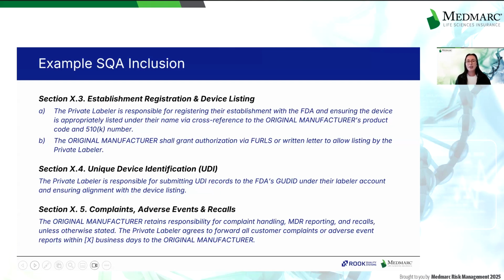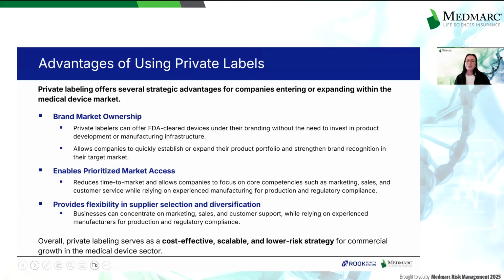And then Section X.5 outlines complaints, adverse events, and recalls, where the original manufacturer is listed to retain the responsibility for complaint handling, MDR reporting, and recalls, unless otherwise stated. The private labeler agrees to forward all customer complaints or adverse event reports within X business days to the original manufacturer. Now, the X business days is generally going to be a business decision, but it's typically recommended 3 to 5 business days. So what are the advantages of using private labels?